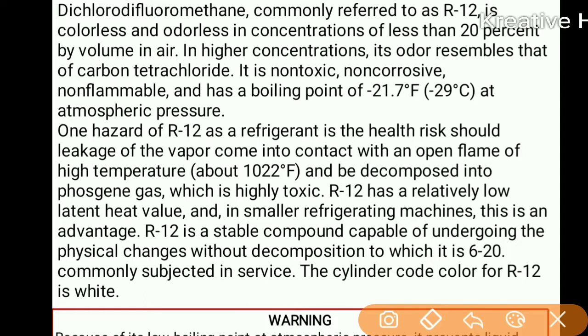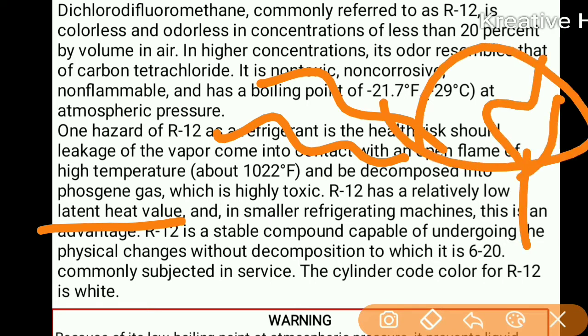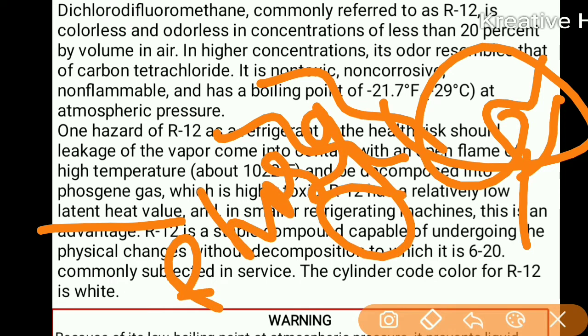Regarding hazards: if there is a leakage of R12 vapor and it comes into contact with an open flame or high temperature, it decomposes into phosgene gas. This is a very highly poisonous gas. So if R12 leaks and there is a flame present, it reacts to produce highly toxic phosgene gas — this is a serious health risk.